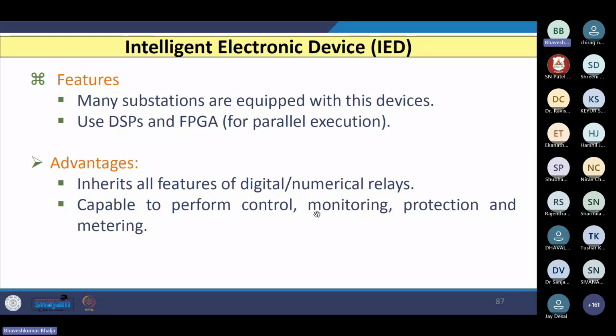And whatever is above the digital or numerical relay is the IED, known as the intelligent electronic device. Manufacturers are still using DSP processors, but now they are trying to replace the DSP processor with FPGA-based processors. But it is still at a research level; nobody has installed it in a utility or anywhere in the system. The reason they call it an IED is that it can have communication, protection, control and measurement, all these features, right? Even some limited backup storage is also there. That's why the utilities are moving towards IED.